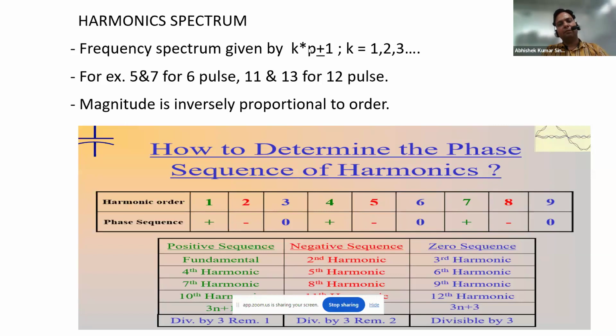So just put 6 at the place of P. If you will see, this is P. So 6 plus minus 1. 6 minus 1 is equal to 5, and 6 plus 1 is equal to 7. It means it will produce fifth and seventh harmonics. But it will also produce 11th and 13th. How? If we put an integer value in this K. So 2 into 6 plus minus 1, that is 12 plus 1 and 12 minus 1. So it can produce either 11 or 13. It can produce either 5 or 7. Okay, this will depend upon the OEM. Suppose we are purchasing from ABB, then the rotation can be something different. If we are purchasing from Schneider or anyone, that will depend. So it can produce any one, like 5th or 7th, 11th or 13th, like this.